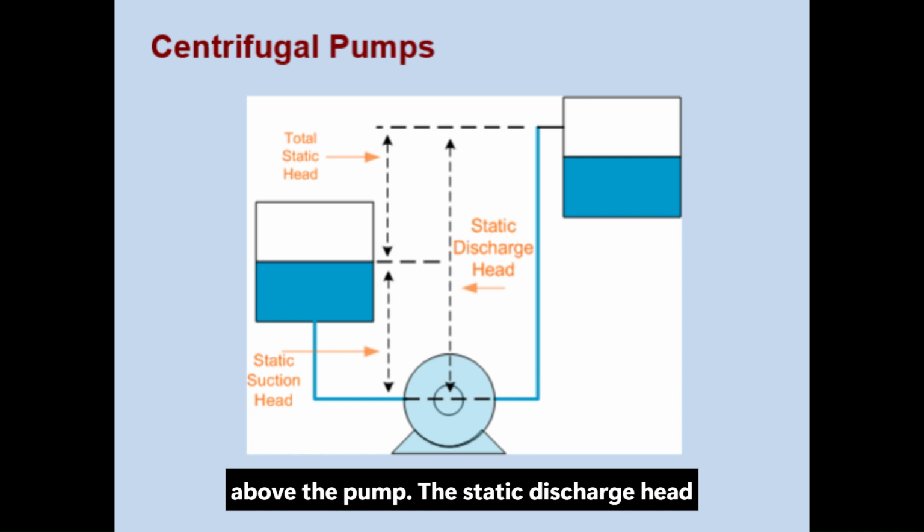The static discharge head is measured vertically from the pump centerline to the discharge exit point. Understanding this measurement is essential for correctly calculating the total head requirements of a pump installation.